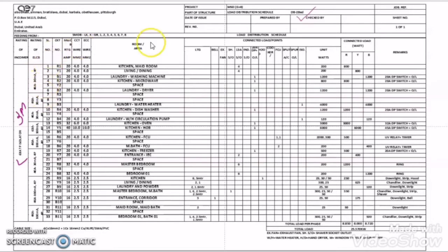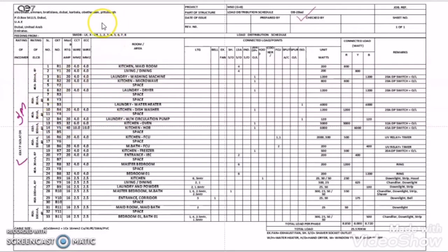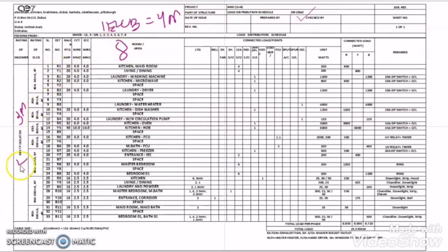Now let us check how many sections are there in this final distribution board — there are total eight sections. Each section has either 30 milliampere or 100 milliampere four pole ELCB, and each ELCB is equivalent to four modules. So eight ELCBs will have 8 × 4 = 32 modules.